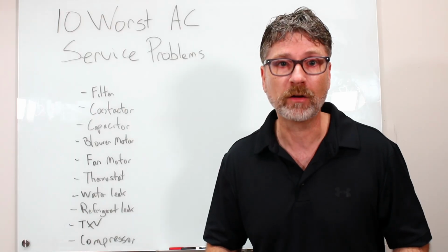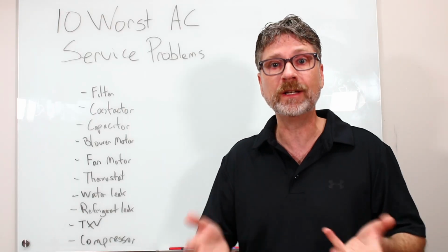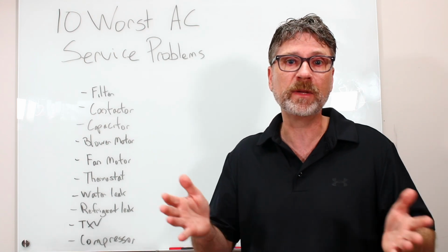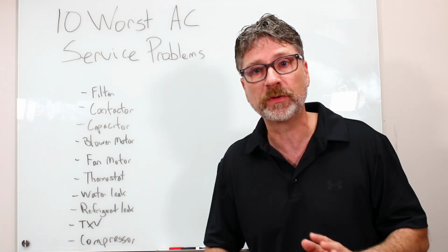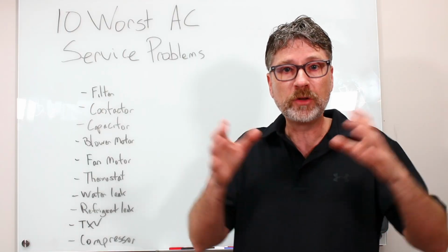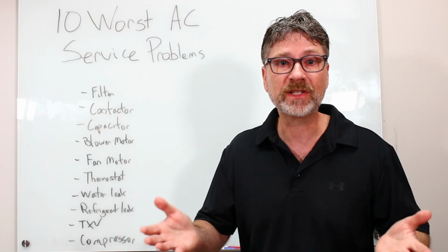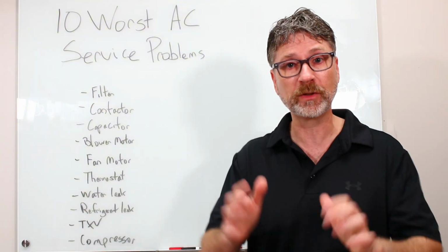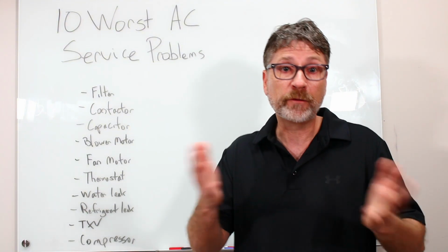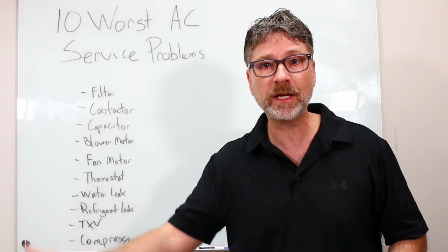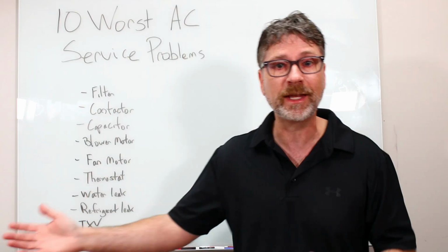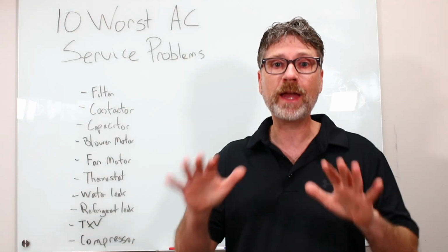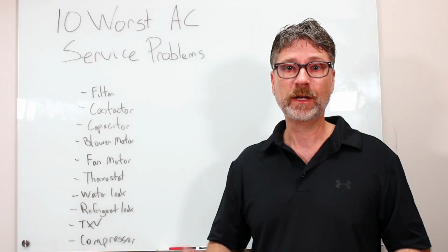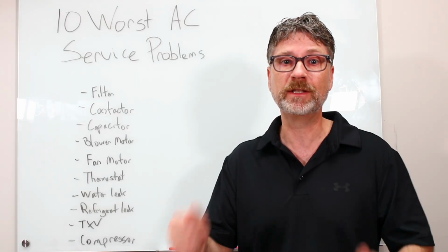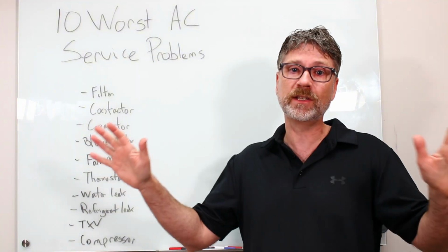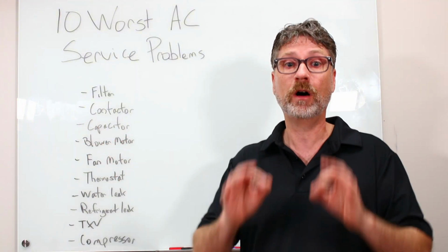Accelerating failure are things like overheating the outdoor unit and or running it out of oil. Overheating can be caused by letting the outdoor unit get clogged with debris or even suffocating it with a too close privacy fence. The refrigerant itself provides the oil for the compressor. It's really mixed into the refrigerant. If there is a refrigerant leak or the refrigerant line gets kinked or it's just too long and the oil settles and can't get back to the compressor, you could dramatically shorten the life of your unit. Replacing a compressor is a really big deal, with out-of-warranty costs easily exceeding $2,500 or more, sometimes a lot more.